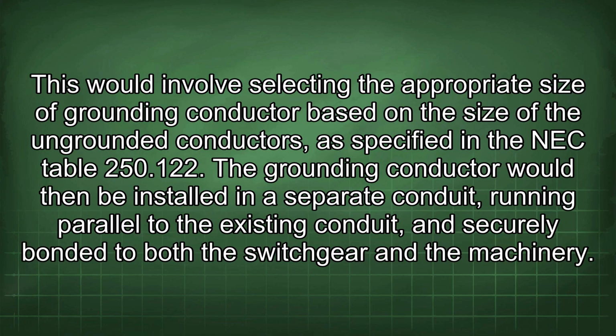This would involve selecting the appropriate size of grounding conductor based on the size of the ungrounded conductors, as specified in the NEC Table 250.122. The grounding conductor would then be installed in a separate conduit running parallel to the existing conduit and securely bonded to both the switchgear and the machinery.